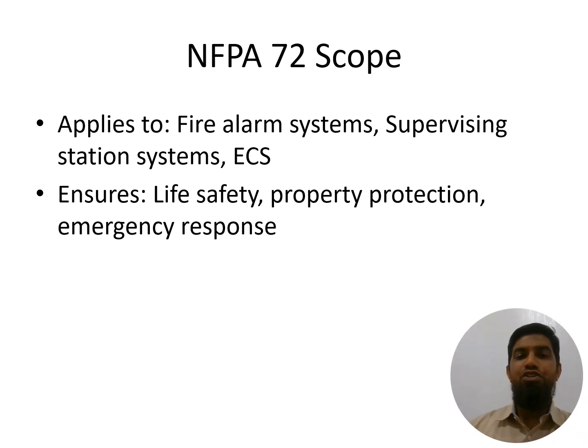The next is chapter 17, initiating devices. All the devices such as smoke detectors, heat detectors, manual stations, and all initiating devices come under this chapter, with a brief explanation of the installation procedures. Chapter 18 guides us for notification devices, where audibility, visible alarms, and mounting heights are all mentioned. Chapter 21 explains emergency control functions such as door release, HVAC shutdowns, and elevator recall. The next chapter is chapter 23, protected premises systems, which covers the requirements of fire alarm panels. The last chapter is chapter 24, emergency communication systems, also called mass notification and voice evacuation systems.